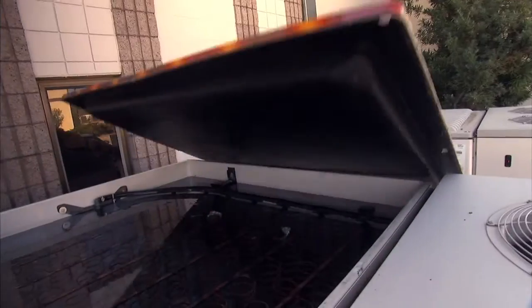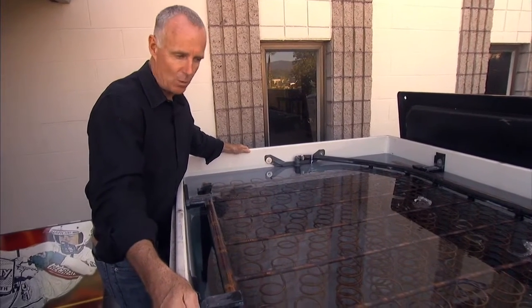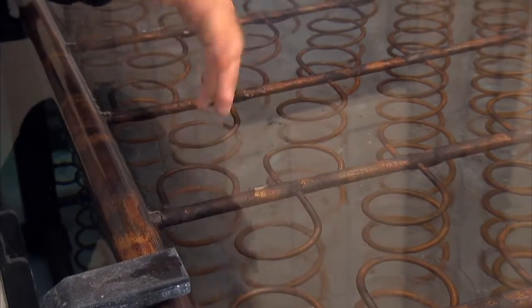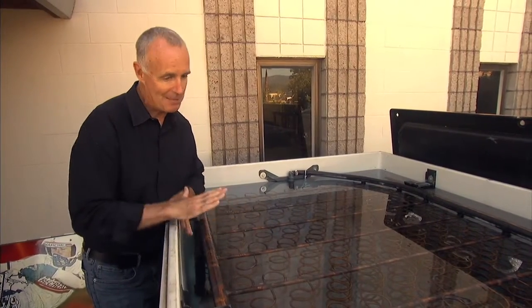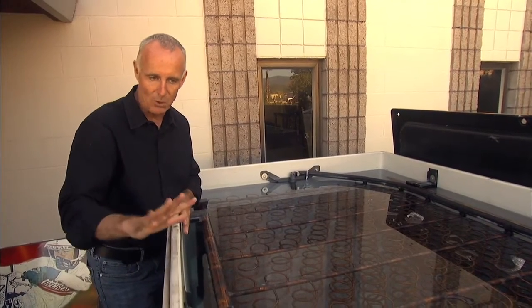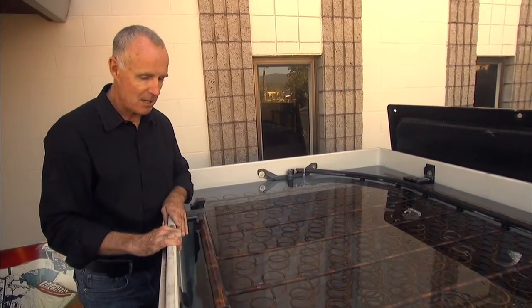The Ice Bear is an insulated tank filled with 450 gallons of water. As you can see, this is where ice is forming around these copper coils. All these coils go down, and now warm refrigerant is going to circulate through the ice, come out icy cold, go back up to the air conditioning, and that's where it's blowing this now icy cold air — not from the air conditioner anymore, but from this Ice Bear.